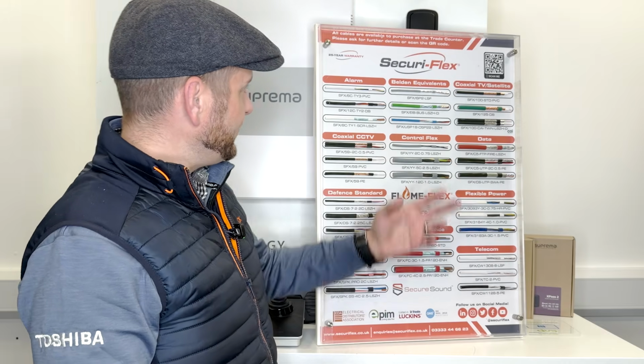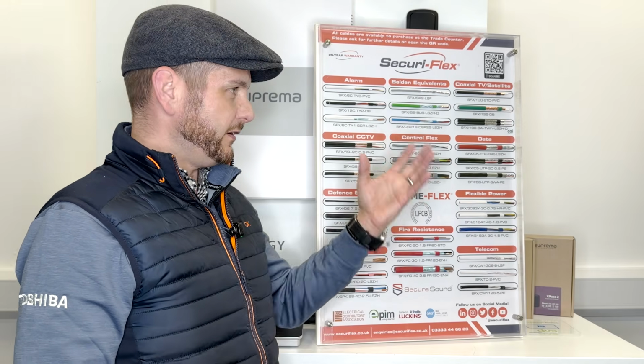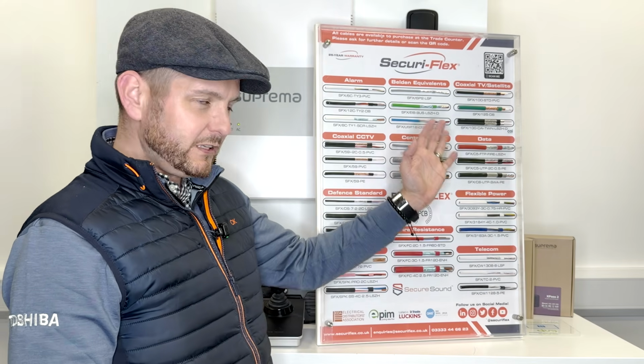Now moving on to the reader. All readers require a cable, and generally it will be Belden equivalent or Belden cable for the reader, and it could be a 4-core, 6-core or 8-core. Again, we can help and advise on that. The Belden, if it needs Belden, is for the data element and to power the reader itself, and Belden or Belden equivalent cable is very immune to RF interference, which means the signal is likely to work consistently and give you a trouble-free access control system.